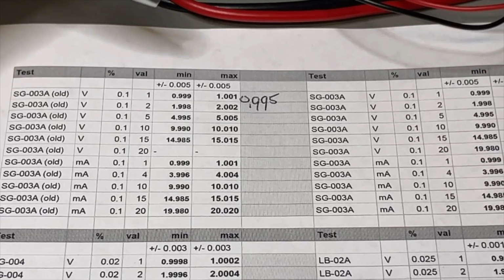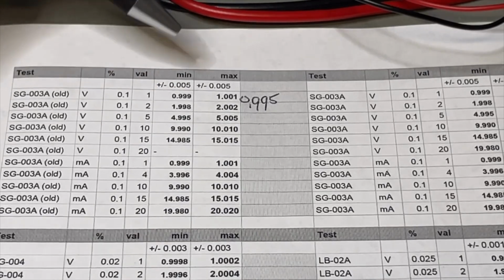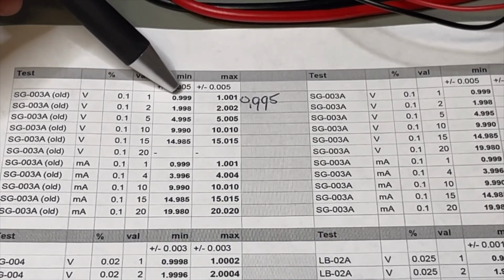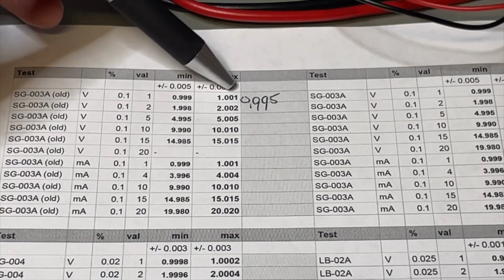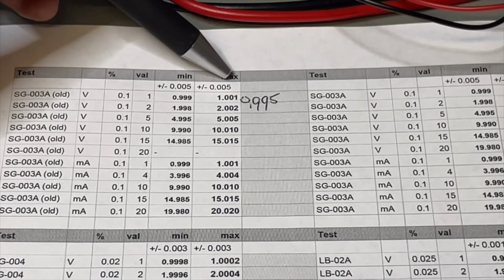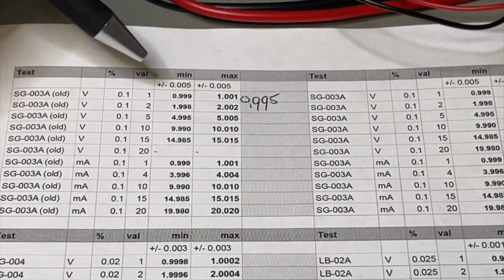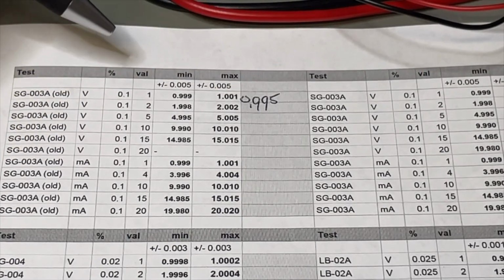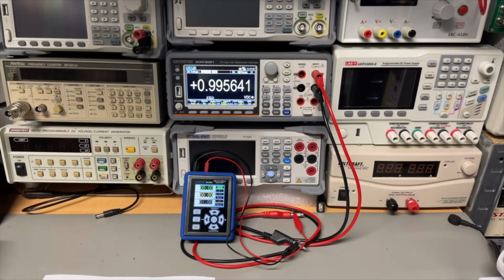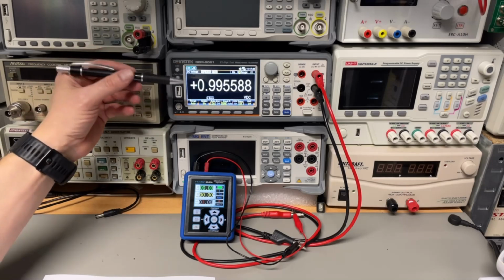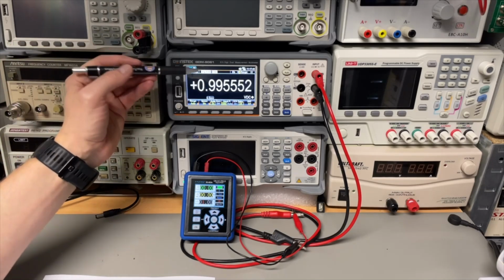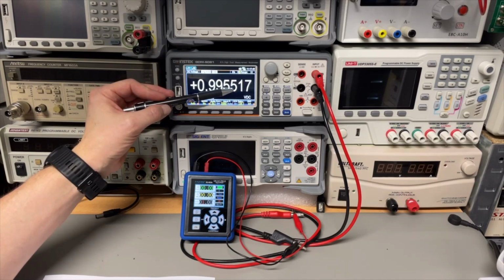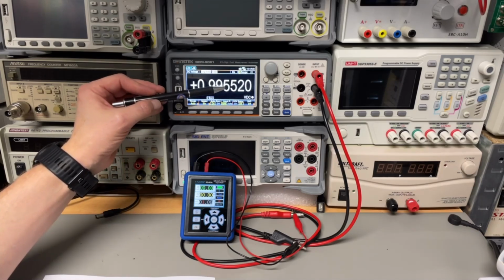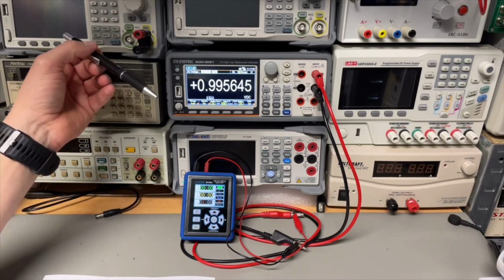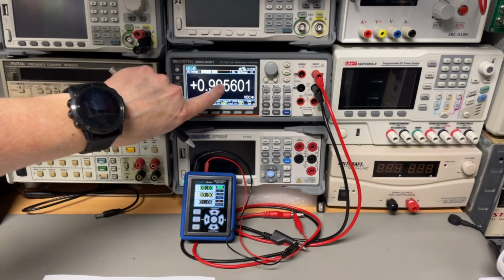The rest I'll do in time lapse, but to explain: if it were 0.1% off a value of 1, it should be between 0.999 and 1.001, but the last digits here are 005, so added together that's exactly 1 volt - so it is good. You can see on the multimeter why it's limited to these 3 1/2 digit, 3200 counts, because the stability jumps a little, but that's okay since they said it would be within 0.1% plus or minus 5 digits at this precision, so it is actually exactly within spec.